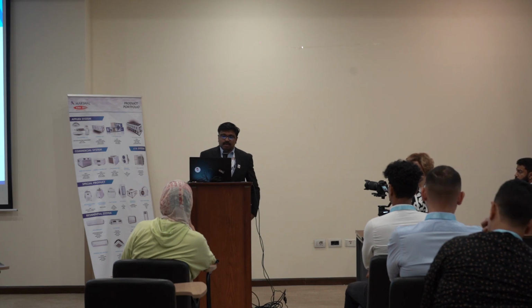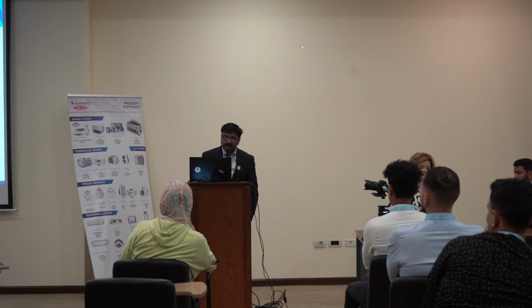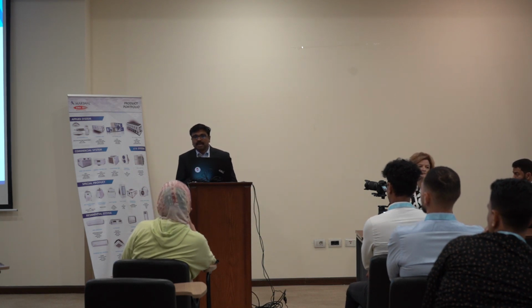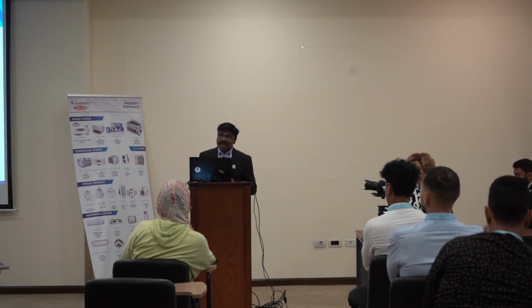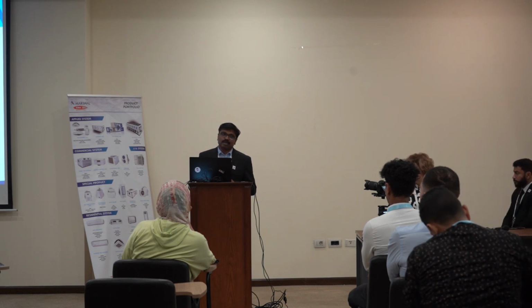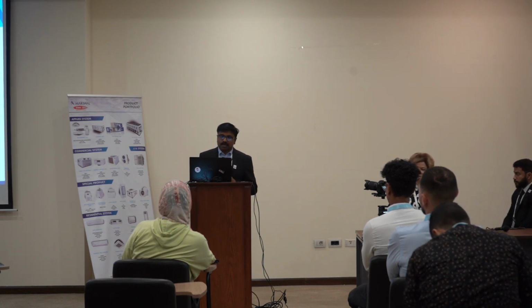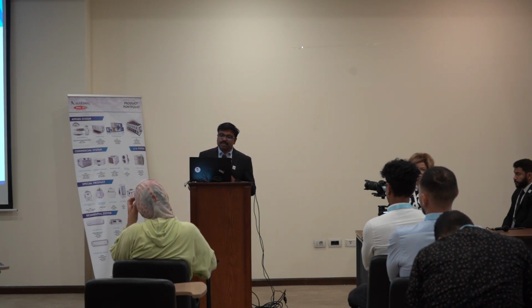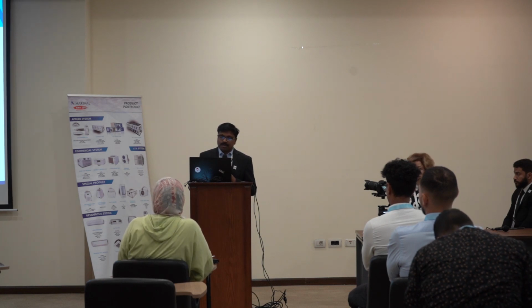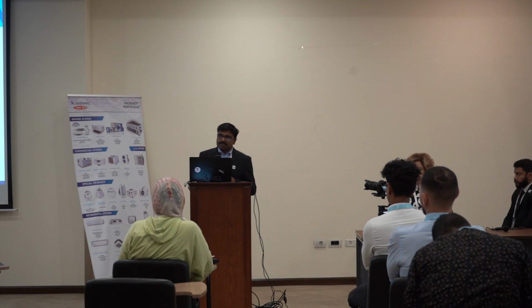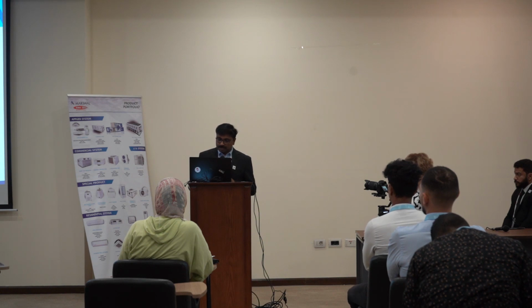And from the end user concept, when we take the residential or commercial segment, the main things the user expects are flexibility, comfort, compact design, sound level, smart systems, and life cycle cost. This is the actual strength of VRF, and we developed these products to address these issues. When we talk about our AVR, the unique innovations, lineup and capability, I will take you through the capacity range. We can provide the VRF system with a maximum capacity of 78 tons, that is 96 HP, 32 HP into 3 modules. That is the largest in the industry.